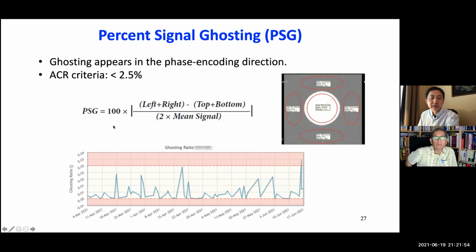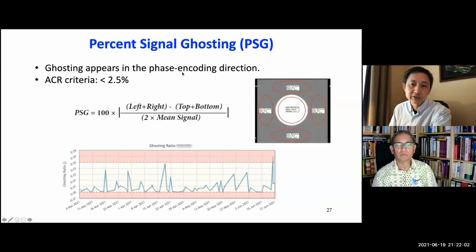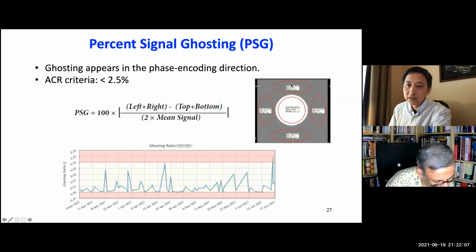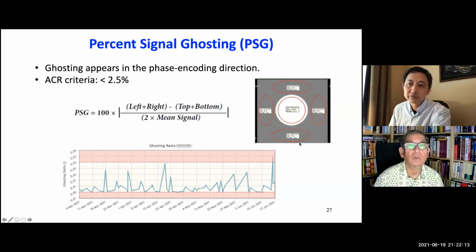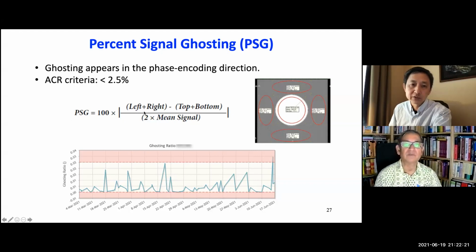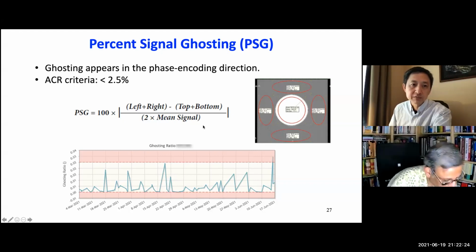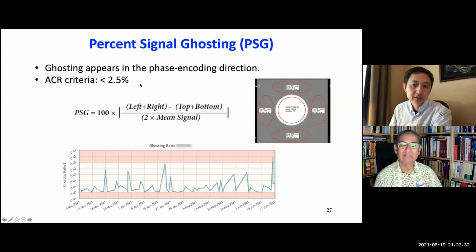Another test is percent signal ghosting. So we know ghosting comes from the instability of the system, and it will show up in the phase encoding direction. So if we put 4 ROIs, left, right, and anterior, posterior, one of the directions should be phase encoding and the other should be frequency encoding. So we average one direction and the other direction and subtract the two, that gives us the amount of ghosting. So this is the definition of the percent signal ghosting. And in this case 2.5% is the criterion by ACR.